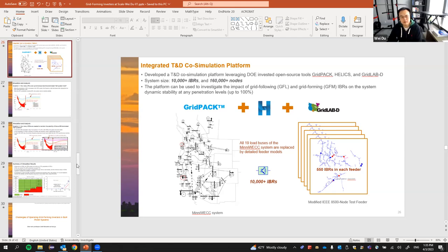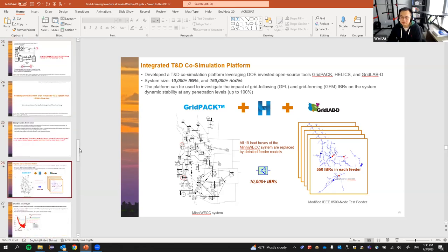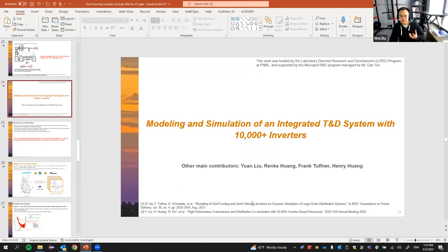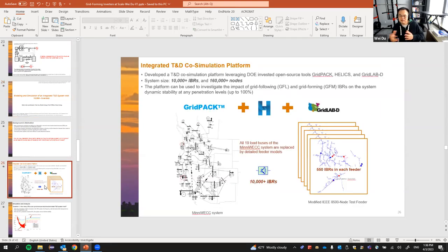Okay, the first question: in GridLAB-D, we developed the grid forming and grid following inverter models. GridLAB-D itself is just a three-phase phasor model, so we developed three-phase phasor models of grid forming and grid following inverters. This is published in a paper, but that paper only shows a feeder with 10 inverters. After that, we tried adding 550 inverters on the 8500 node test feeder. It still works pretty well, but runs slower. I think it takes about 1 minute to run 1 second of simulation. And that's for the GridLAB-D only simulation.